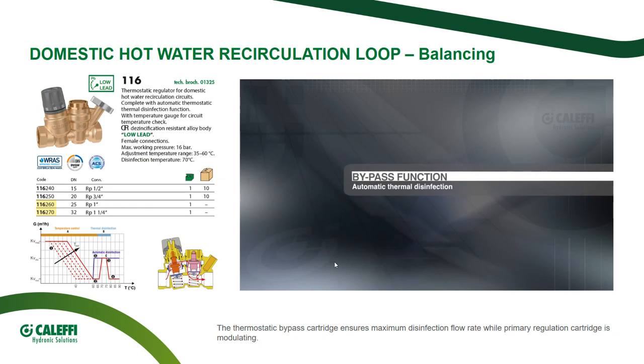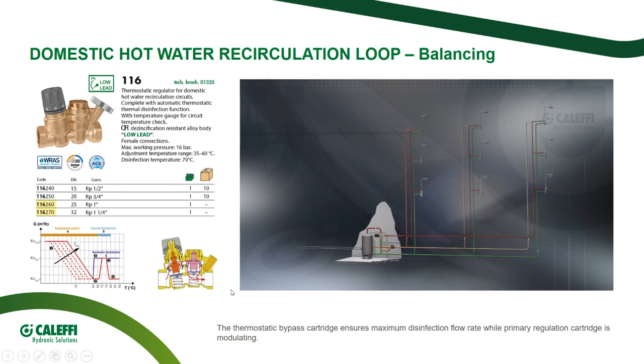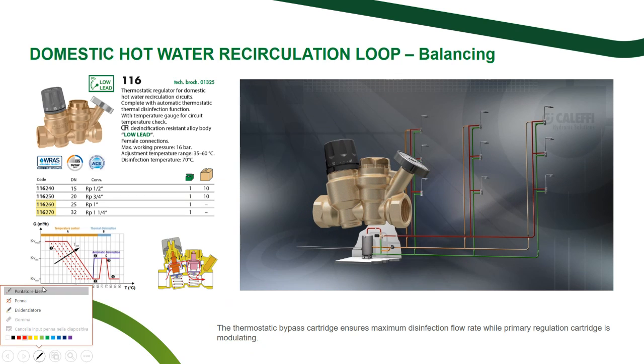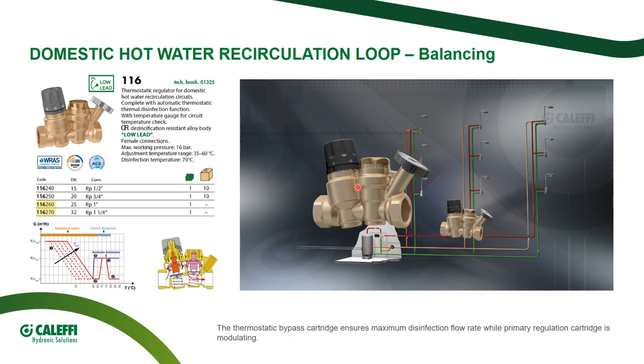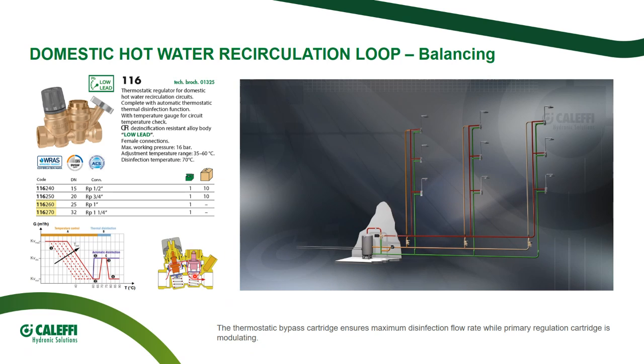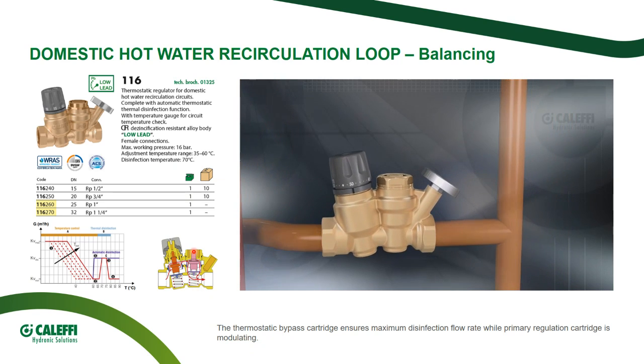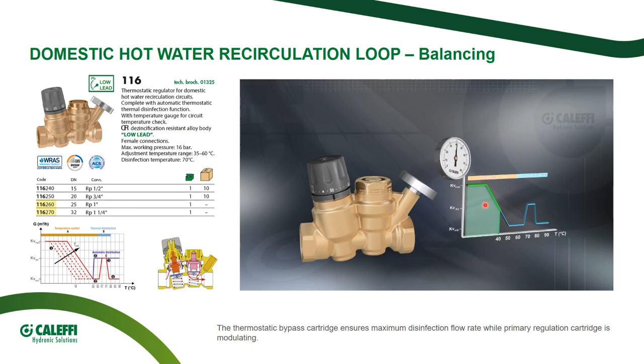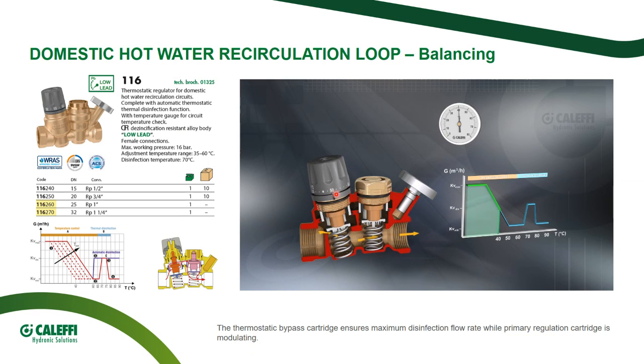What about the compatibility with thermal disinfection? There are two ways. One way is thermostatic and the other one is electrothermal. It is basically a bypass function. So this is the installation of a thermostatic balancing valve with integrated recirculation disinfection cartridge. So we saw before, when the set point temperature for the primary regulating cartridge is reached, the valve gets to the minimum flow. But as we get 68 or more degrees, the valve starts opening the bypass way. So I will never miss my disinfection flow when it is needed.